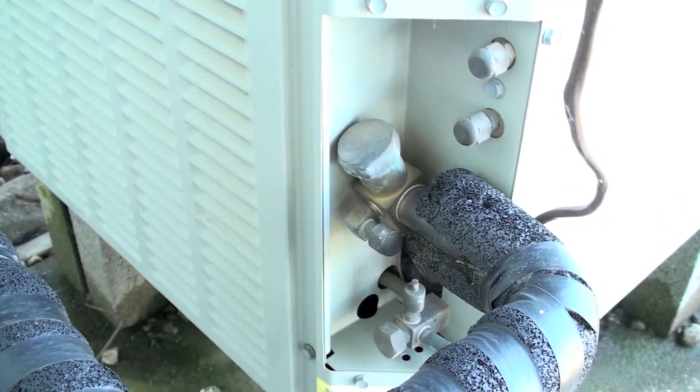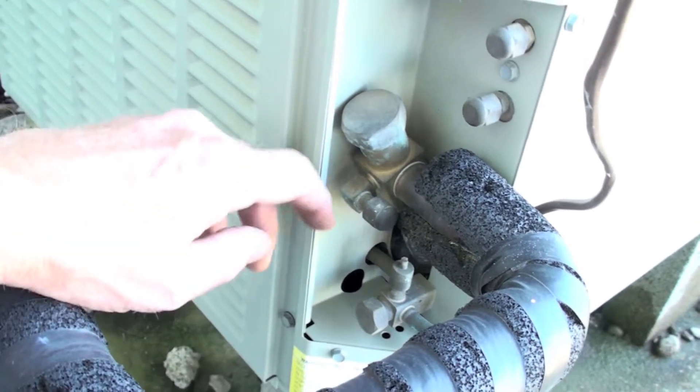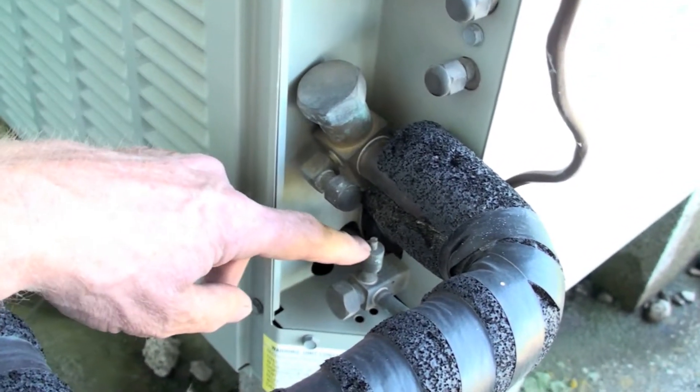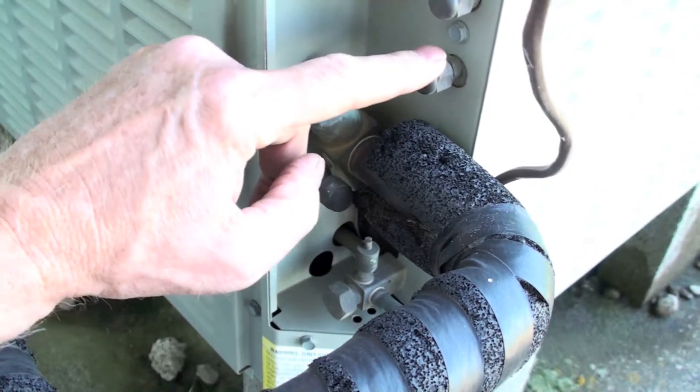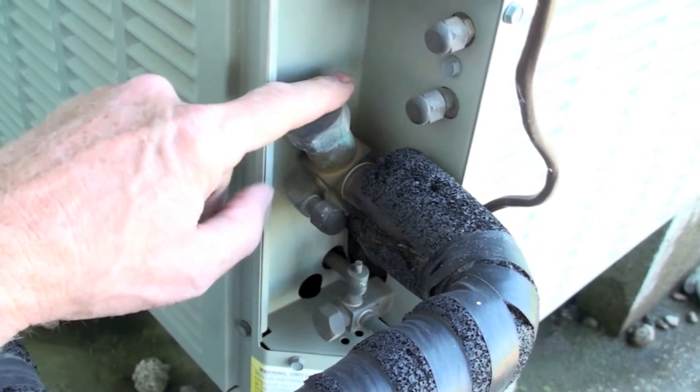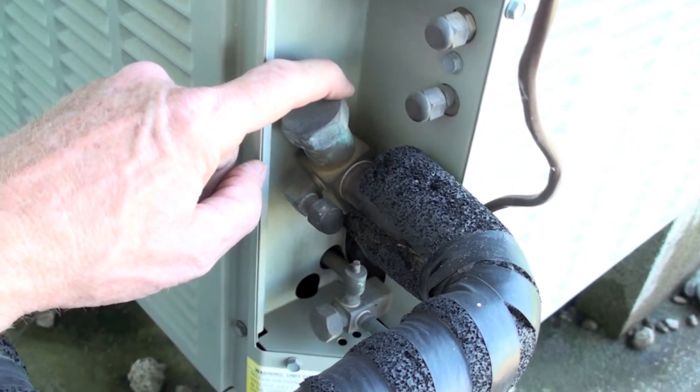Okay, here we're looking at the service taps. This is a line set tap here, line set tap here. Here's a couple of internal service taps. Because this is a heat pump, this is a service valve—the suction service valve.